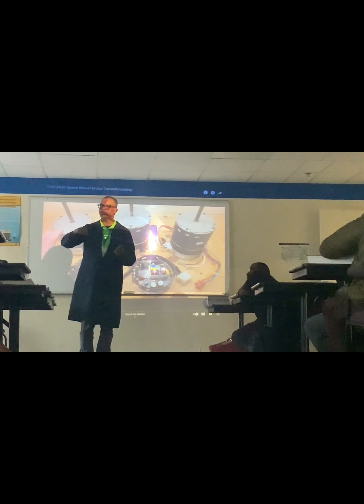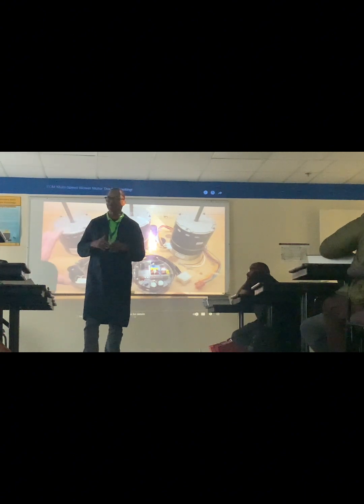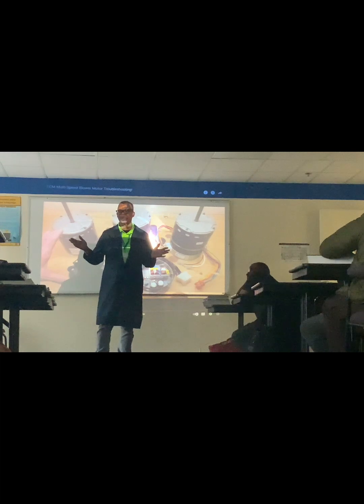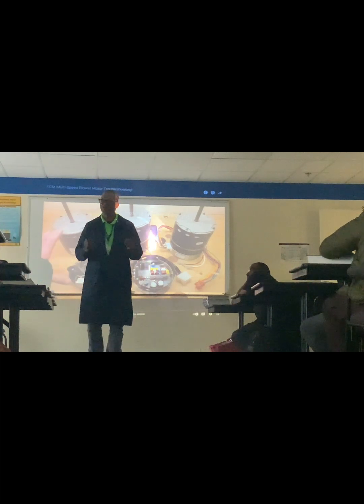If I'm at 30 hertz, what am I running? If 60 hertz equals 100%, that's half speed. So if the motor is 800 CFM at full speed, running at 30 hertz means I'm running 400 CFM.